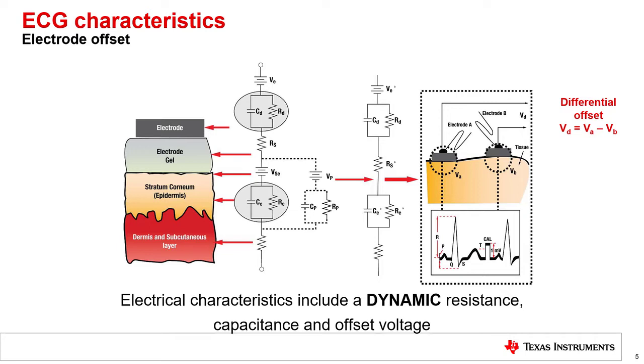The diagram on the right illustrates how two electrodes may be resting at different DC potentials, VA and VB. The difference between them is the differential offset voltage for that lead, or VD. Standards for ECG equipment specify that the ECG must still be measurable in plus or minus 300 millivolts of differential offset.